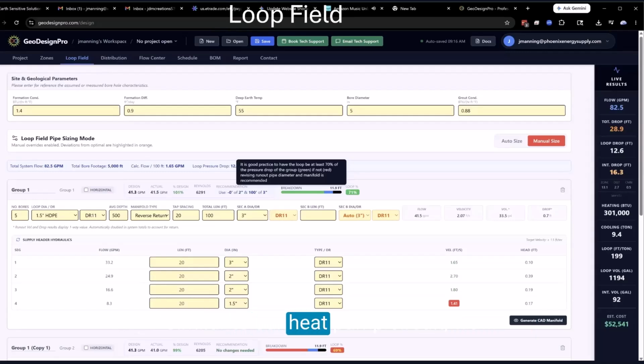Similar to our heat pump circuit, we have a similar color-coded feedback of where that pressure drop is occurring. Is it in the run-out pipe? Is it in the vertical loop? Or is it in the reverse return manifold? If it's green, that tells us our loop is at least 70% of the total pressure drop. Go down to the bottom of the screen and you'll see our next group, labeled Group 2. The red indicates that particular loop is at 69%. It's feedback to open your eyes to options you may have to improve pressure drop and avoid excessive pressure drop with run-out pipe and manifolds.